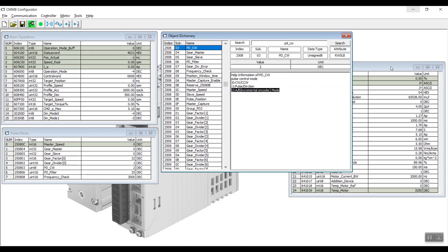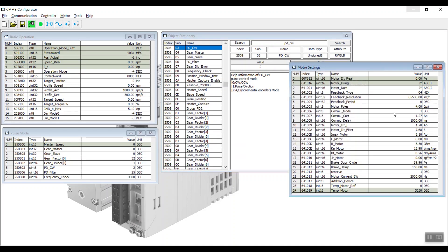Next, we'll look at the motor settings. We can see that the feedback resolution is 65536 pulses per revolution. This is different from what we have set at the CMMT. Hence, we need to do some calculation to obtain the gear factor.